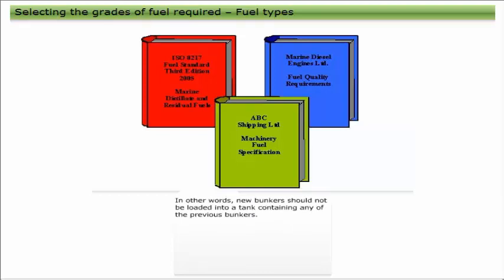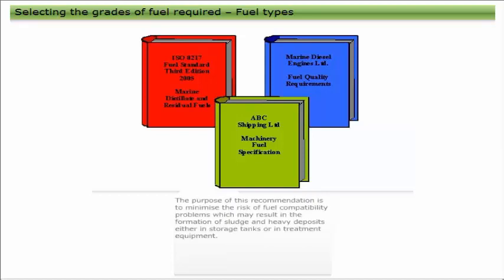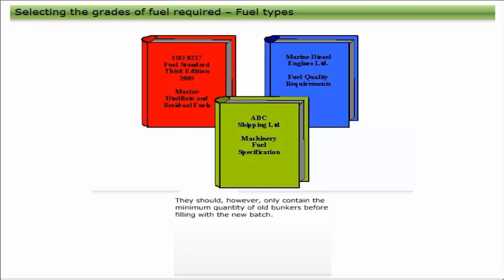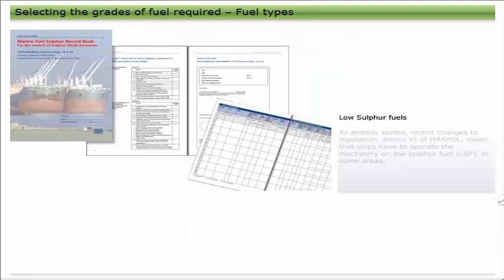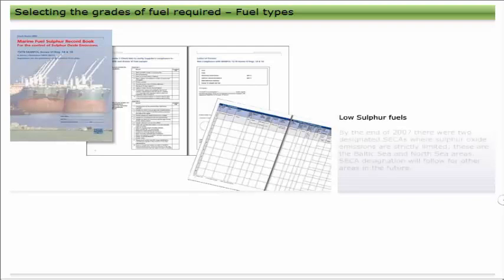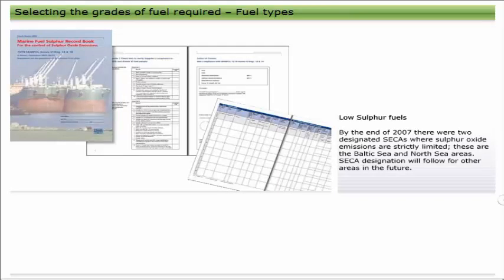It is recommended that fuels from different sources, particularly residual fuels, should not be mixed in storage — new bunkers should not be loaded into a tank containing any of the previous bunkers. This minimizes the risk of fuel compatibility problems which may result in the formation of sludge and heavy deposits in storage tanks or treatment equipment. Mixtures of residual fuels can become unstable even if the original fuels were stable, so mixing should be avoided whenever possible. In practice, tanks should contain the minimum quantity of old bunkers before filling with a new batch. By the end of 2007 there were two designated SECAs where sulfur oxide emissions are strictly limited: the Baltic Sea and North Sea areas.